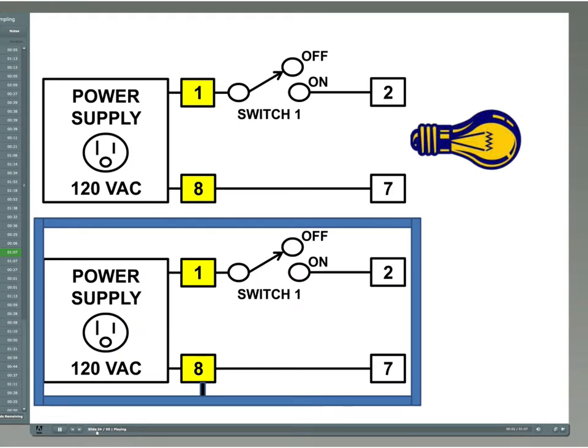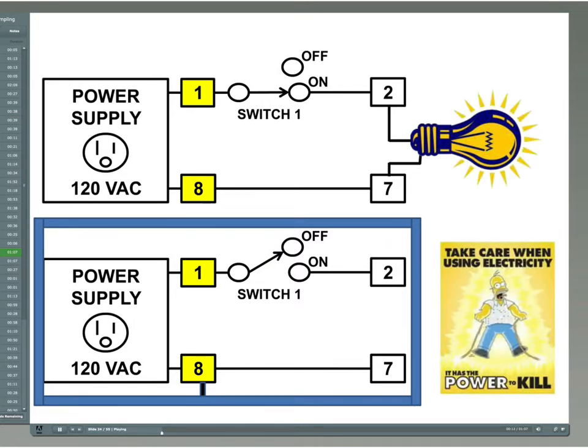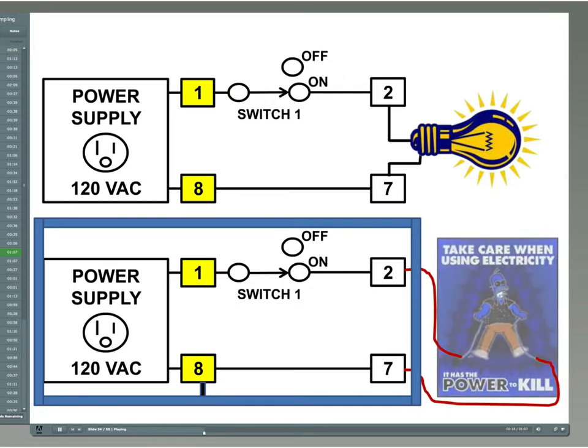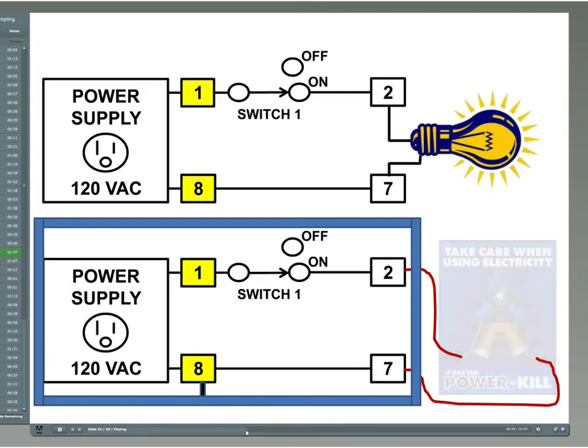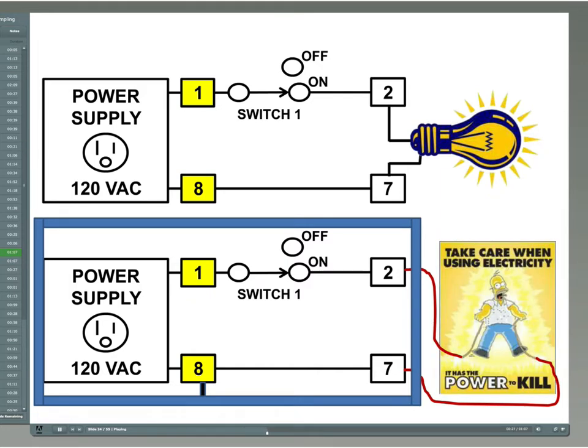This series of circuits illustrates how loads become energized, whether they were meant to be energized or not. High pressure seeks low pressure, and will push electrons through filaments as well as a once beating heart. Enclosures are grounded, and the return side of the circuit is wired directly to the enclosure. Touching the enclosure with one hand and at the same time touching terminal 1 or 2 with another limb can electrocute a person. When Homer is touching the high pressure side of the circuit, but not the return side, he has not completed the circuit. Therefore, the current is not flowing through his heart, and he is still alive. If he completes the circuit by just merely touching the enclosure door, the high pressure on his right hand will seek the low pressure on his left hand, and Homer could be a dead man.